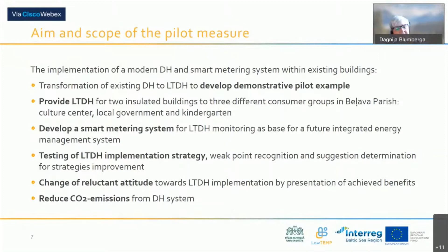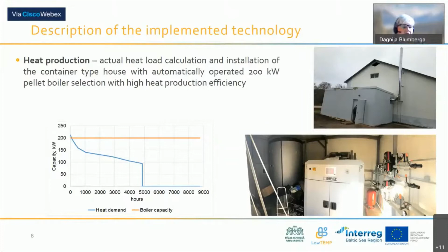Next slide, please. Here you see the calculations of the district heating load duration curve. It's important to understand the load when outdoor temperature is lowest—around 200 hours where the outside temperature is minus 25 degrees centigrade. Calculations show the load is approximately 200 kilowatts, maybe a little more, and Gulbene municipality agreed to install a pellet boiler with an installed capacity of 200 kilowatts in that case.